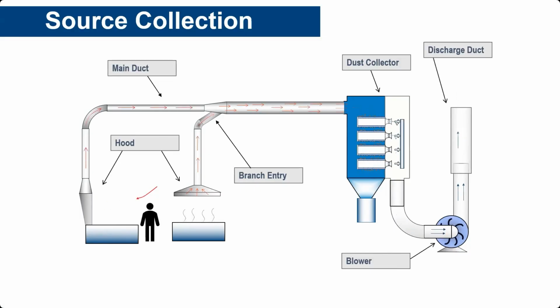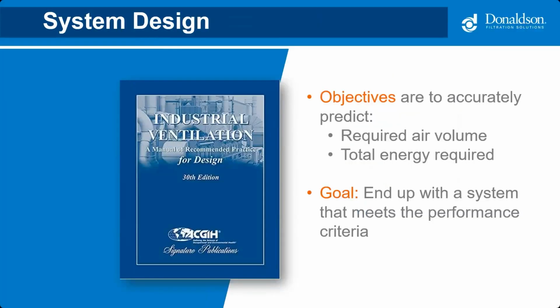These systems are a sum of the individual parts and are designed based on the characteristics of the dust or fume and various application factors. If one component is poorly designed, the whole system can be affected. In system design, we have two main objectives. We want to accurately predict how much air in CFM is required to effectively capture and control dust at its point of generation. And we also want to know the total energy and horsepower required to produce those airflows.